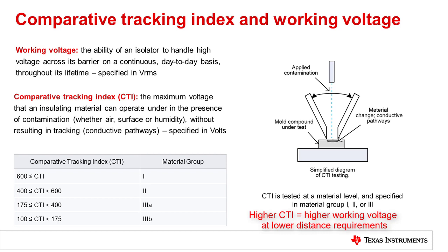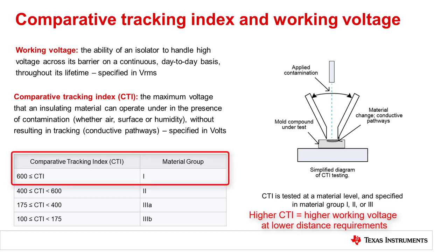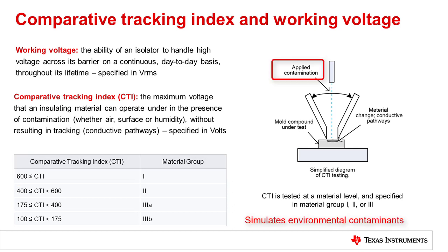A device with higher CTI levels equates to a higher quality material level. Material level 1, for example, is the highest quality material for mold compound. With this in mind, higher CTI found in material group 1 requires smaller creepage and clearance distances than those made with lower CTI or higher material group mold compound. TI isolators use material group 1 and offer the highest quality mold compound. As mentioned earlier, material CTI is tested with applied contamination, which in the test environment simulates environmental risks of surface contamination.